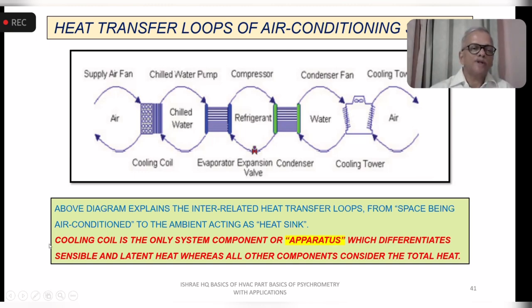Now, an important thing to note is that the cooling coil is the only system component, or apparatus, which differentiates the sensible and latent heat of the space that is being removed. Once it goes to this coil and then to the chilled water and the refrigeration, it is all total heat. There is no more differentiation between sensible and latent. It's only at the coil that this differentiation occurs.